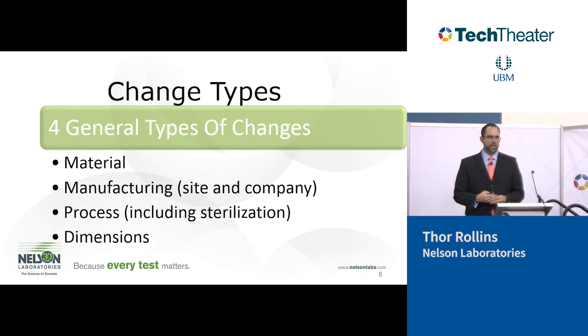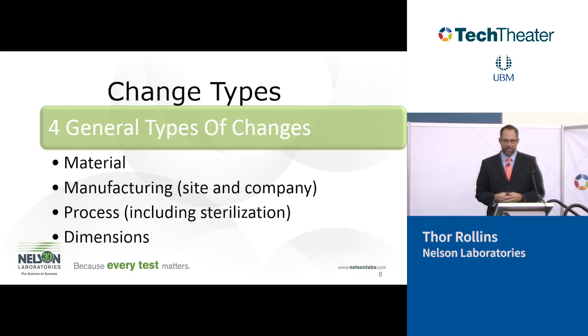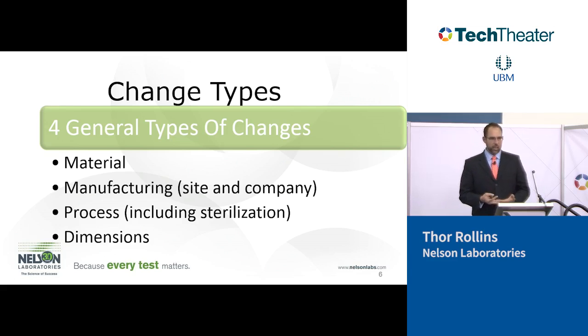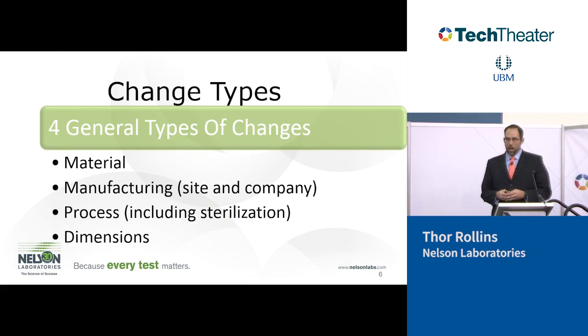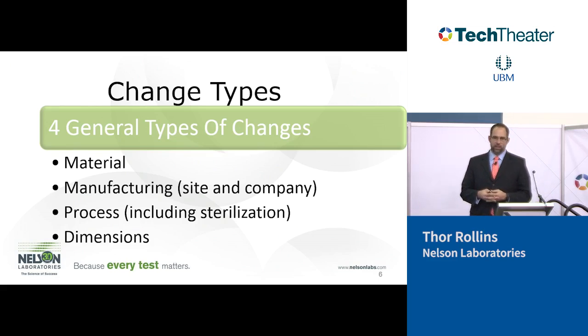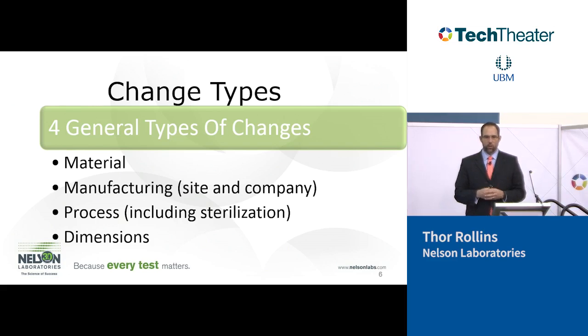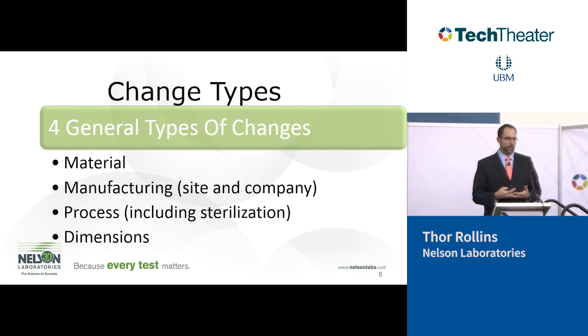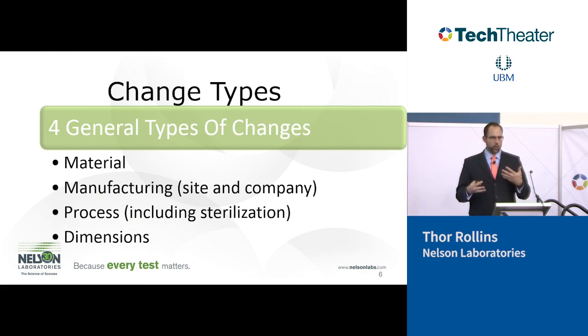So, in my experience, there are 4 general types of changes that I see in medical devices. We have material changes, where we're changing a material in the device, or a manufacturer of the same material. The next change is a manufacturing site, or the company manufacturing that material. A process change, and that includes sterilization. We're changing from gamma to EO, or we're changing an adhesive, an administration, or a mold release to something else, or we're changing dimensions. And sometimes dimensions get overlooked.